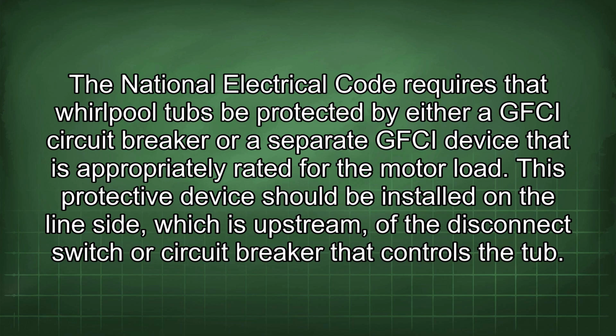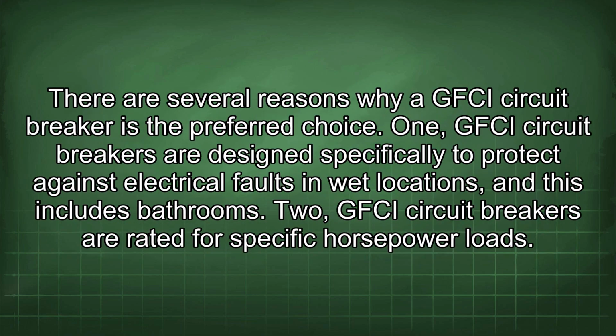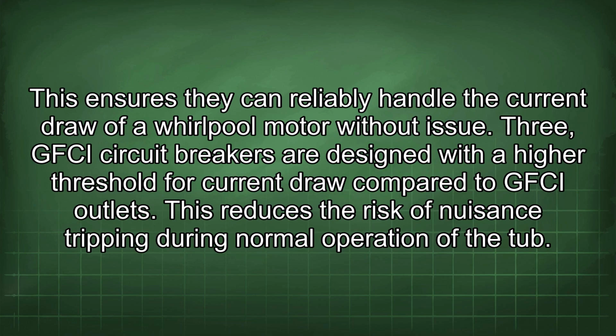that controls the tub. There are several reasons why a GFCI circuit breaker is the preferred choice. 1. GFCI circuit breakers are designed specifically to protect against electrical faults in wet locations, and this includes bathrooms. 2. GFCI circuit breakers are rated for specific horsepower loads. This ensures they can reliably handle the current draw of a whirlpool motor without issue.